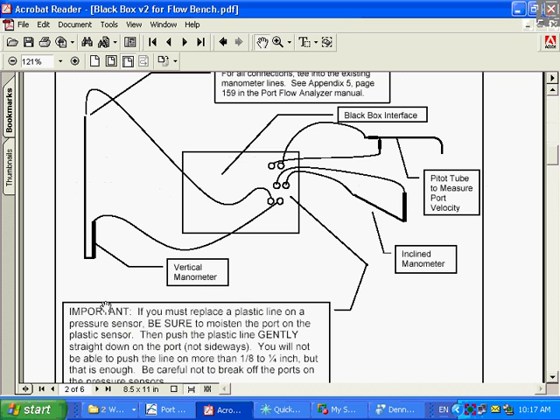In this little diagram, it shows that you tee in these vacuum lines that come with the black box from these different ports, and where they get teed into the actual manometers on your flow bench. And what you do is, let's say you got this line here going over to this lower port on the manometer. You cut a couple inches off this line, and with the tees that come with it, tee in between, remove the flow bench's pressure line from the manometer, and take that tee and a little piece you cut off and tee it in there so that you get these pressure sensors seeing the exact same pressure as the manometers.